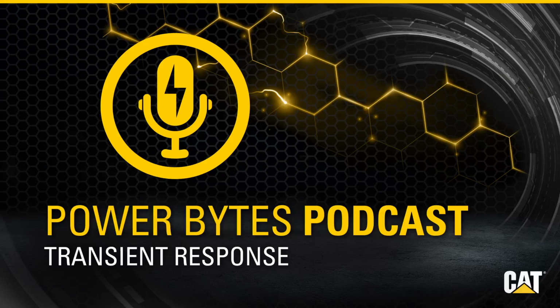So, Bryan, what causes the load on the generator to change so suddenly? So there are several reasons for a sudden change in loads. Things like large motors or other loads can cause sudden changes when they're turned on. If there are several automatic transfer switches in a facility, sometimes when they're changing to transfer the loads onto the generator or to remove the loads, you'll see that as a transient as well. And there are also large sudden demands from transformers. As they're becoming connected to the system, they'll become energized, and that will cause an inrush for the generator as well. So the size of the load and normally the nature of the load will determine the size of the generator's transient response.